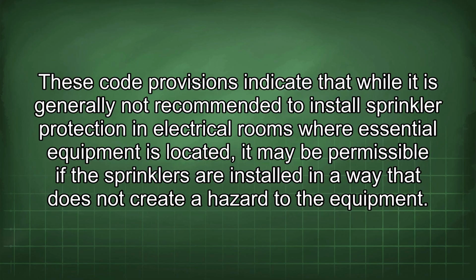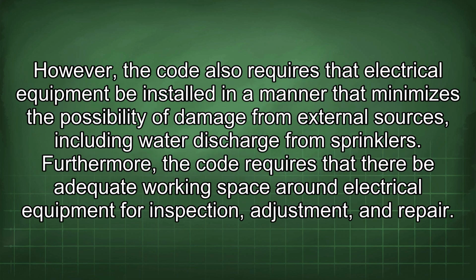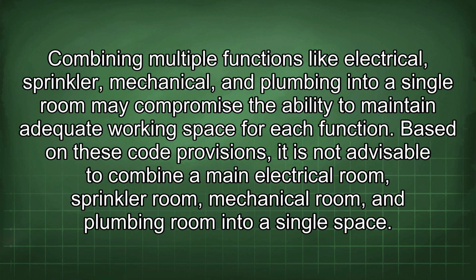These code provisions indicate that while it is generally not recommended to install sprinkler protection in electrical rooms where essential equipment is located, it may be permissible if the sprinklers are installed in a way that does not create a hazard to the equipment. However, the code also requires that electrical equipment be installed in a manner that minimizes the possibility of damage from external sources, including water discharge from sprinklers. Furthermore, the code requires that there be adequate working space around electrical equipment for inspection, adjustment, and repair. Combining multiple functions like electrical, sprinkler, mechanical, and plumbing into a single room may compromise the ability to maintain adequate working space for each function.